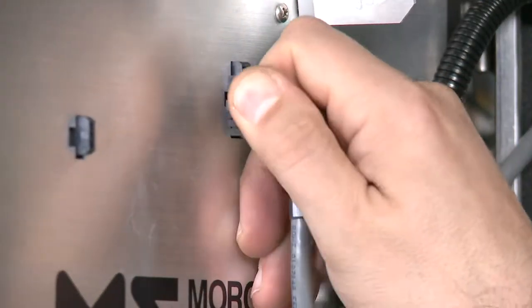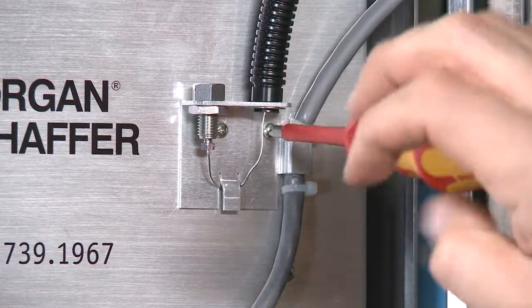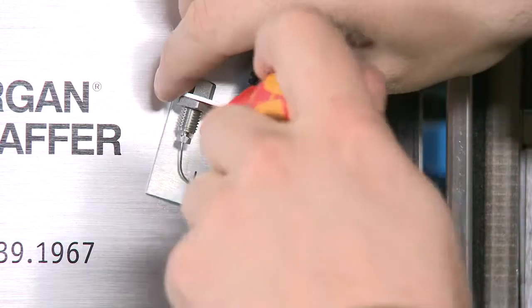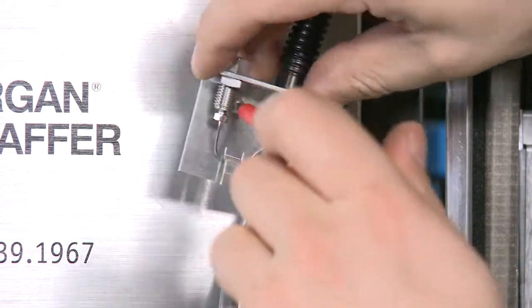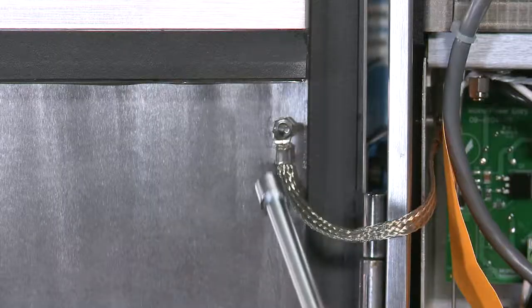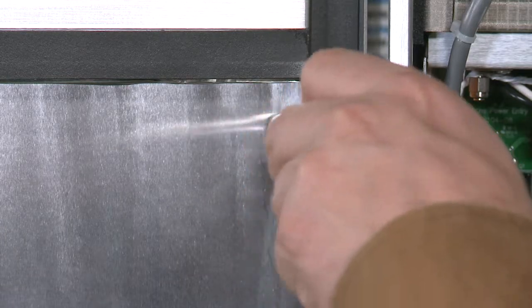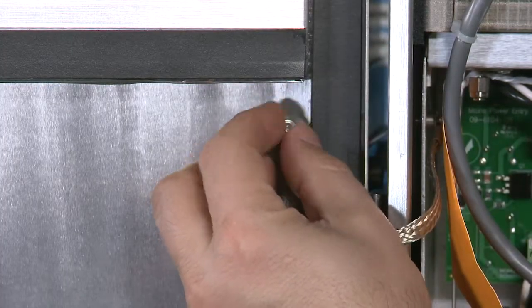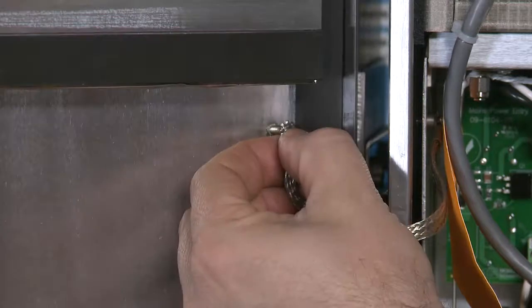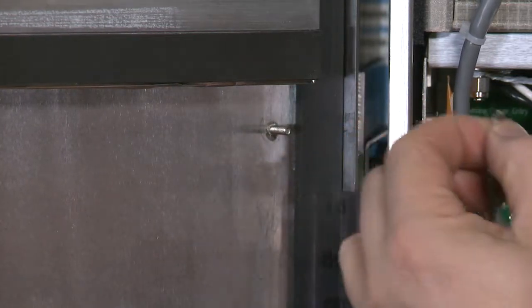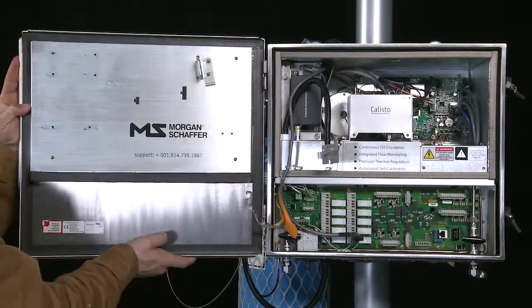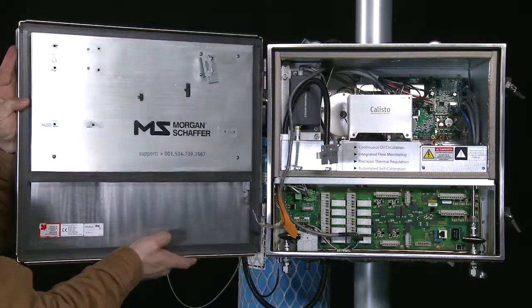Removing the door. Disconnect the display cable. Remove the 2 screws on the bracket using a Phillips No. 1 screwdriver and set the bracket aside. Remove the door ground link using a 5/16" nut driver. Keep the lock washer and the nut. Remove the door by carefully pulling it upwards.